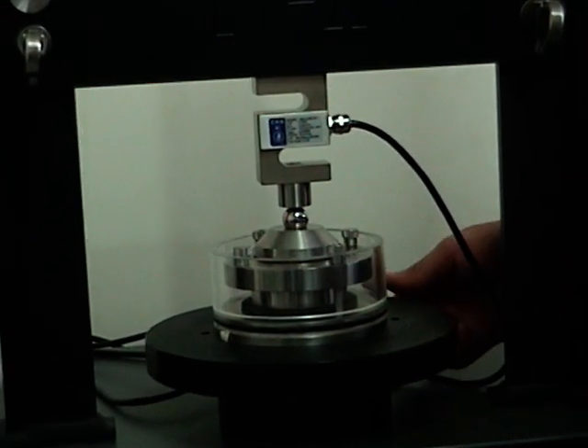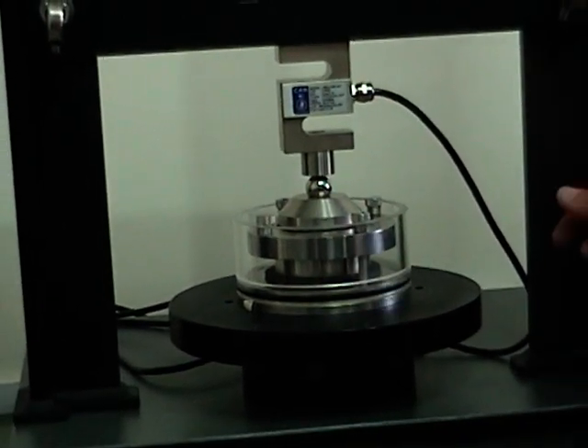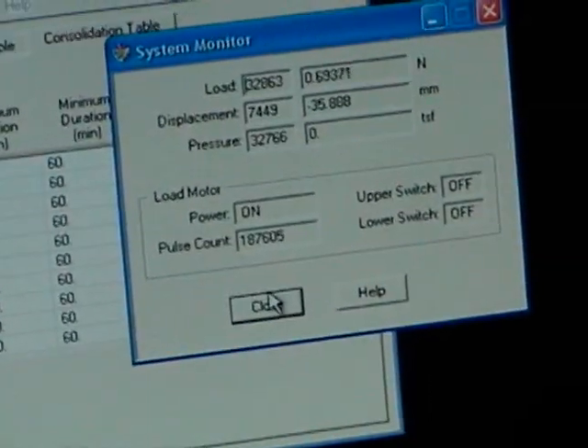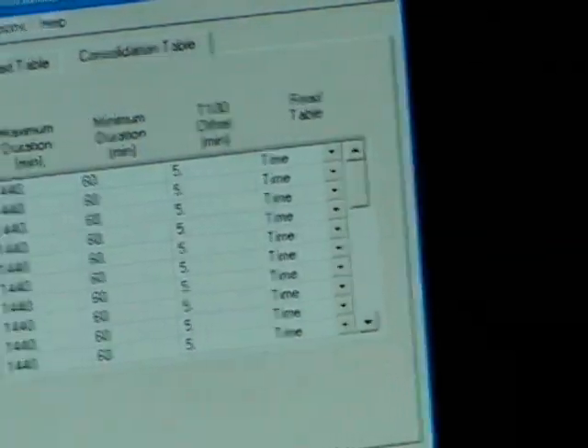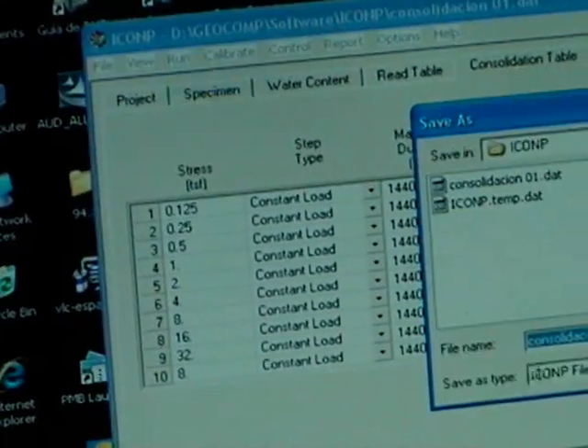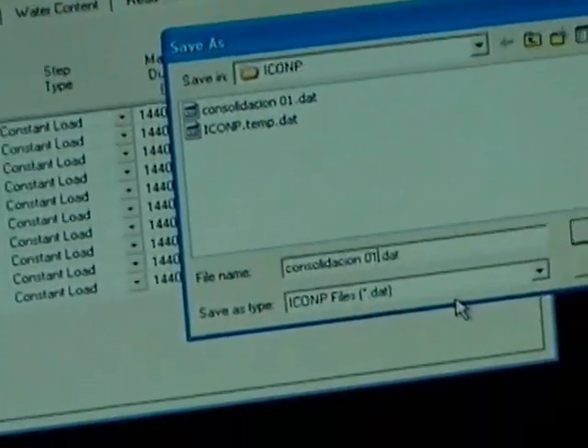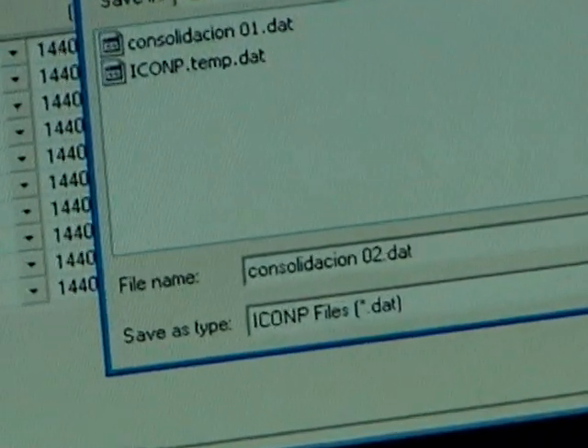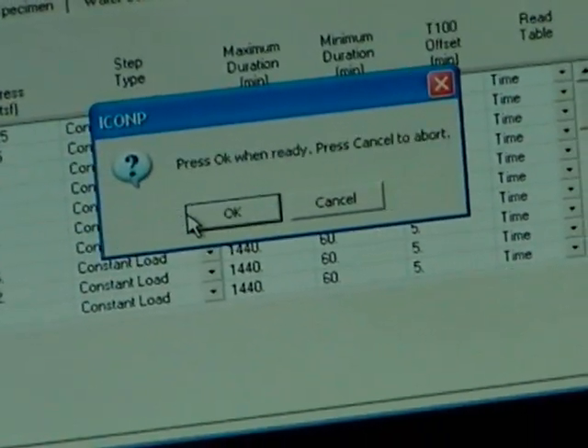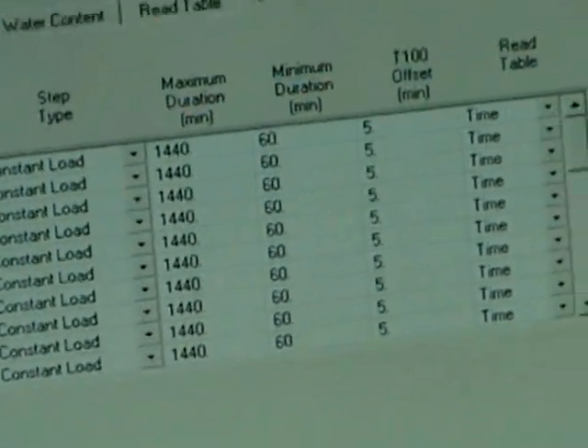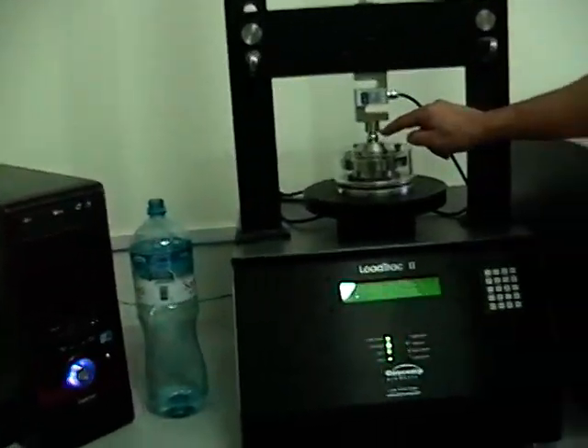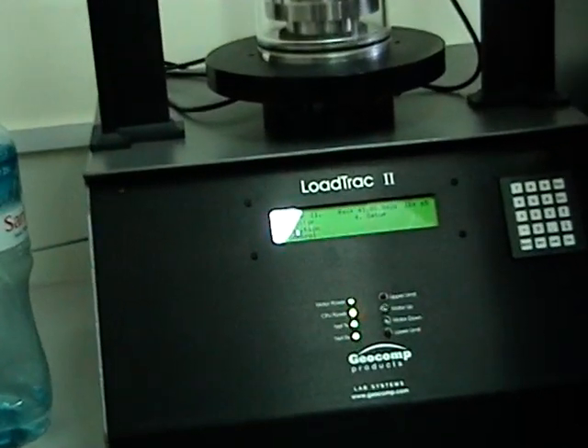Now we go back and we close that and we go to Run, Start. We're going to always give it a different name and you do Save Position Platen. You say yes, and then you wait. Now the platen is going to move up until it touches, until the contact is made between the steel ball and the load cell.